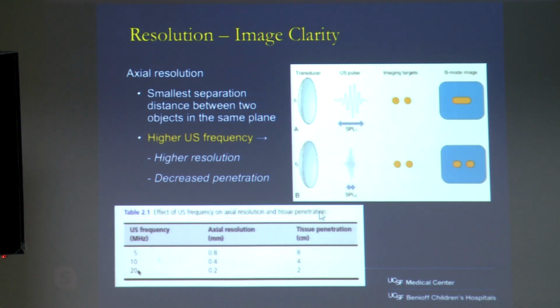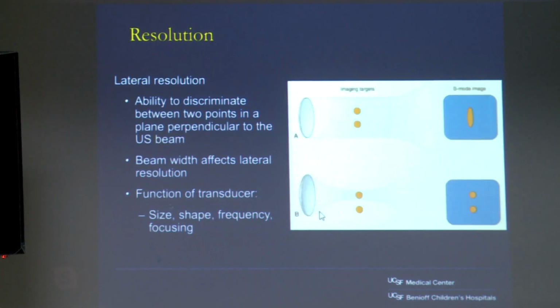That's usually a different mini probe that can be attached for direct evaluation. So that's the frequency. And the lateral resolution is simply if the two structures are side by side, the ability to distinguish them. You can think of it as being in focus versus out of focus. This is a combination of factors related to the scope, the size of the wave, and the frequency. And this is something that's determined automatically by the scope. We don't really adjust for this. This is a built-in feature of the scopes when we use our echo endoscopes.